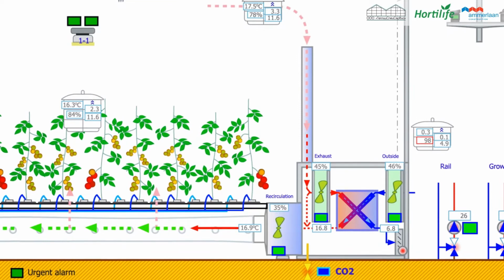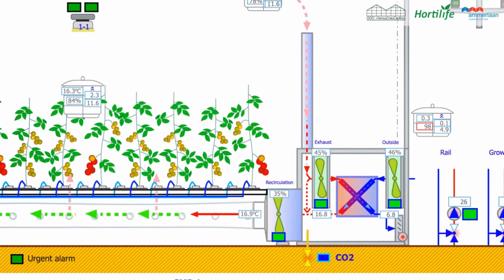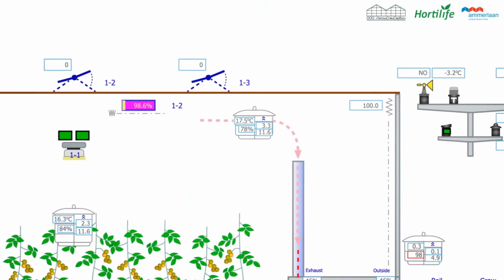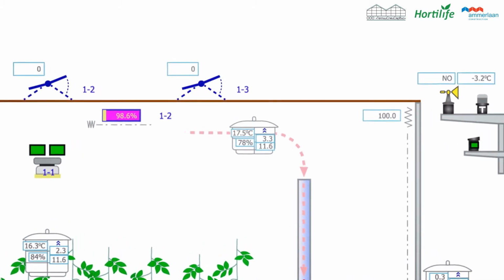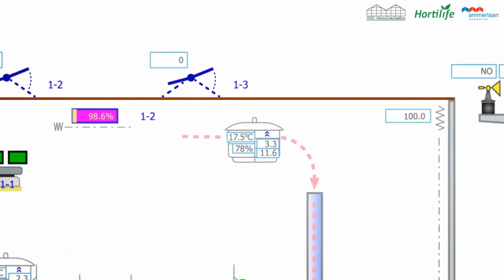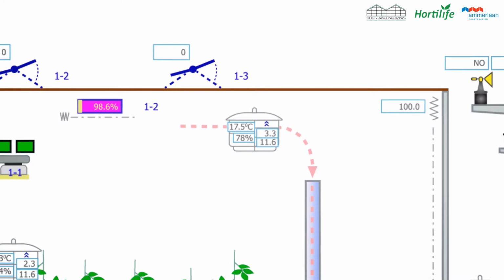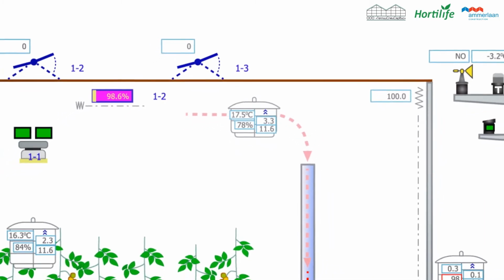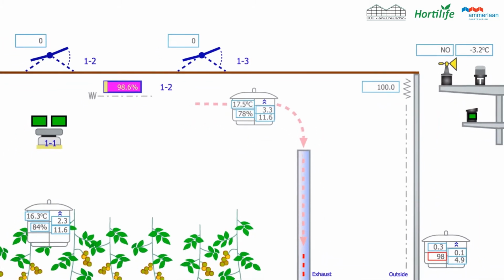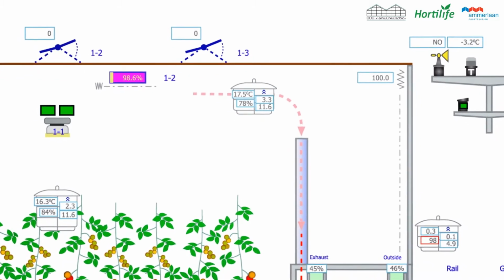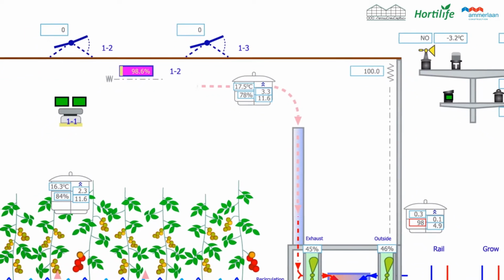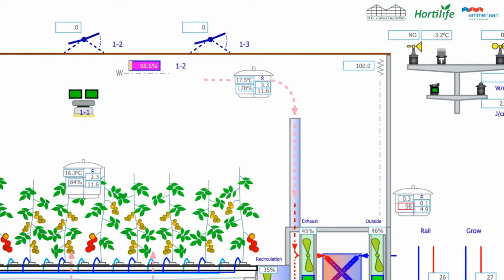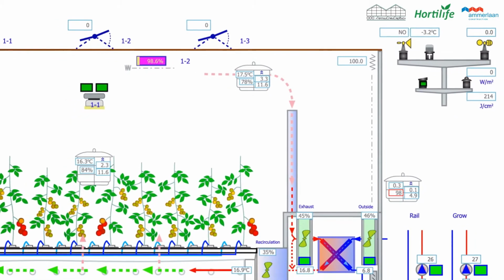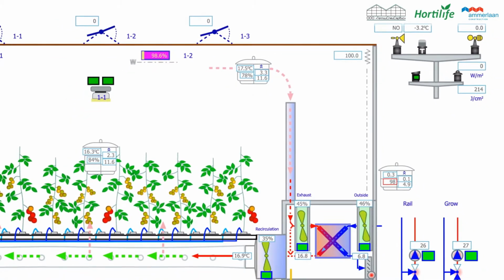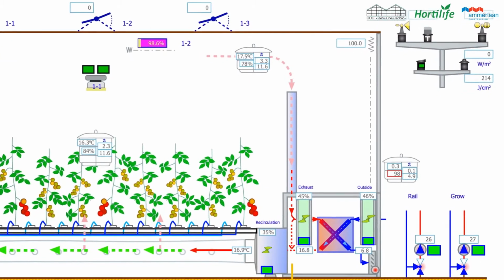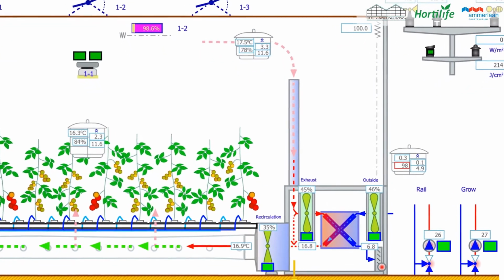The measuring sensor above the plants records a temperature of 17.5 degrees Celsius. Relative humidity is 78%. The absolute humidity is 11.6 grams of water per 1 cubic meter of air, 9.7 grams per kilogram. This value is the same as the humidity value in the area between the plants. In this case, the relative humidity is lower due to a higher temperature. Air goes down the walls to the Air and Energy unit with heat exchanger.